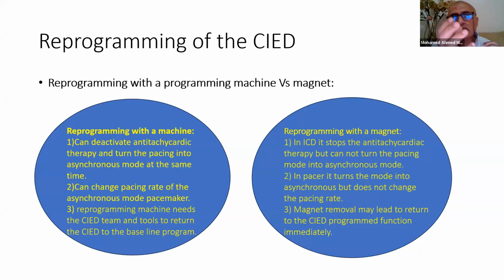It may be an advantage of the magnet that we don't need the CIED team. We don't need the cardiologist to reprogram the device. Once we put the magnet on the device, the reprogramming will begin. But not all the devices can respond to the magnet, because in some devices, during the setting of the device, the effect of the magnet is turned off. So in some devices, when we put a magnet, we will not get any effect. If the magnet is effective, once we remove the magnet from the device, in most cases the effect of the magnet will be reversed, and the device will return back to its original function before putting the magnet.